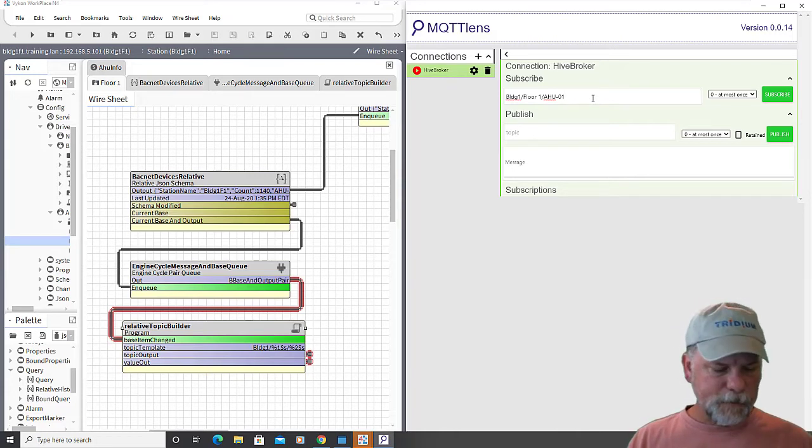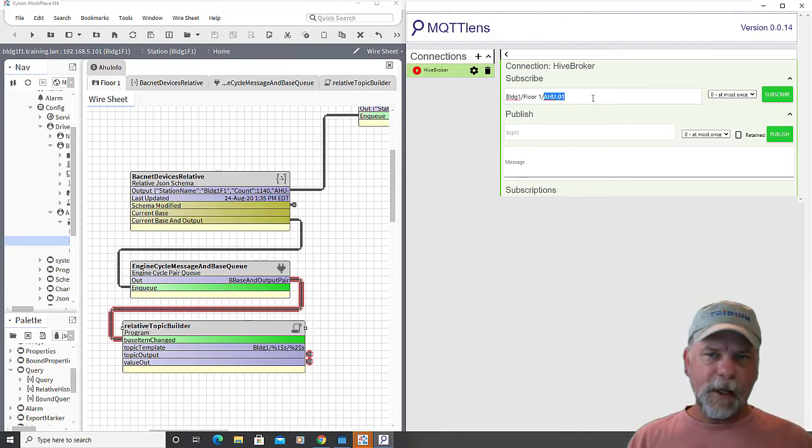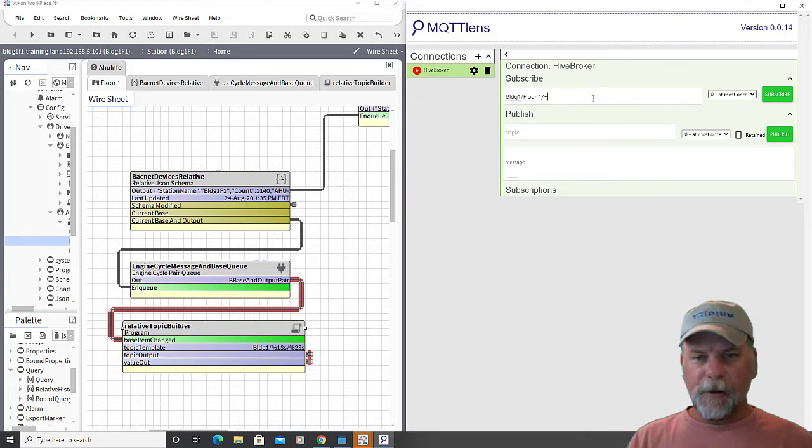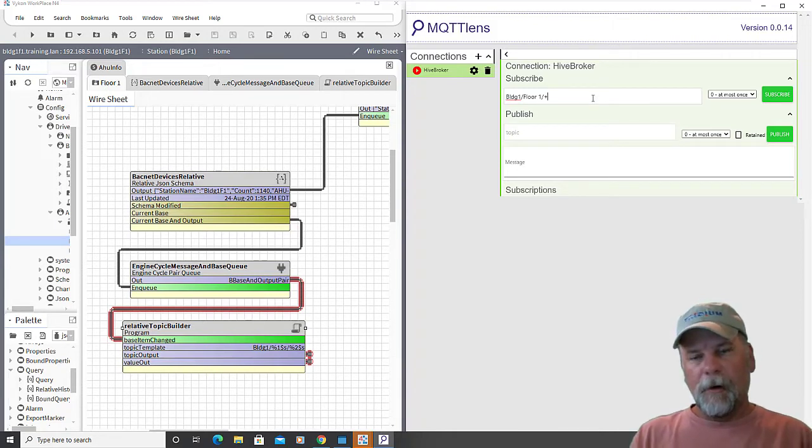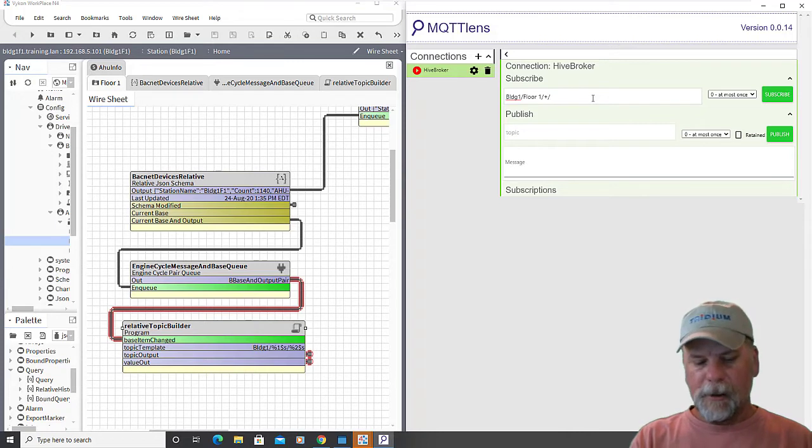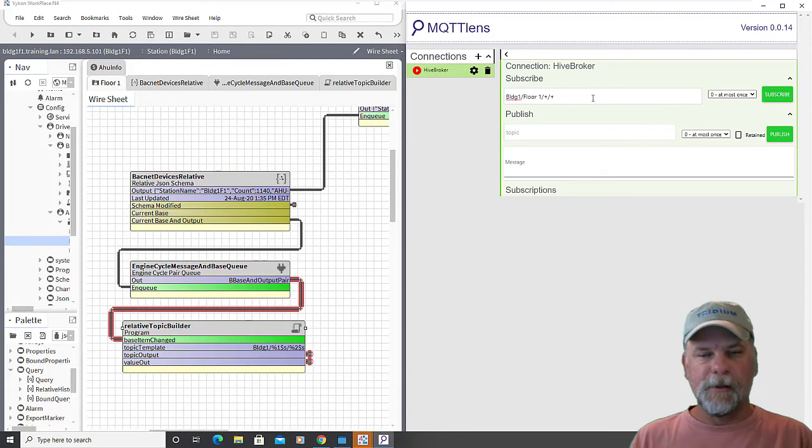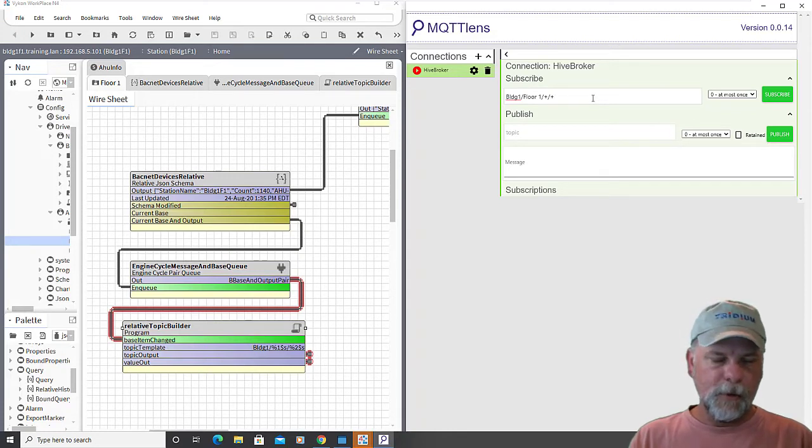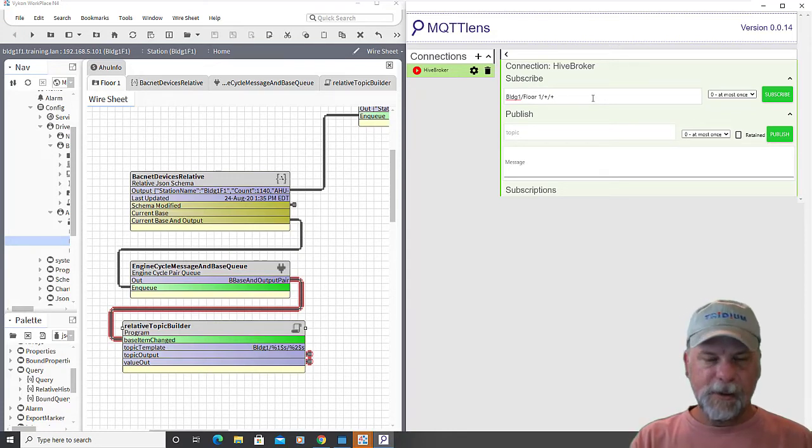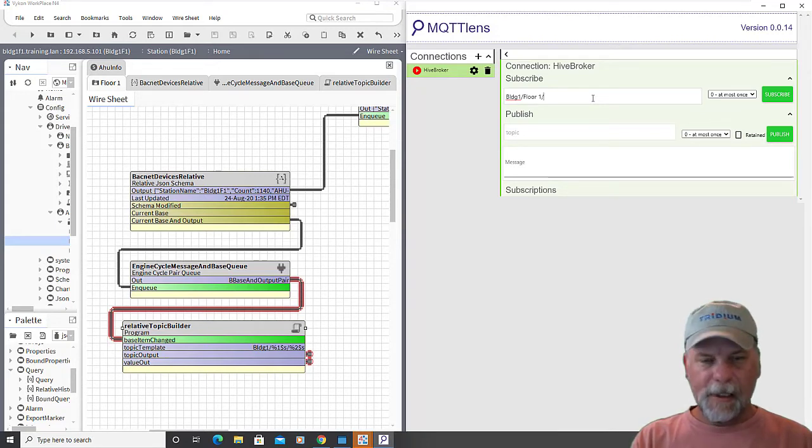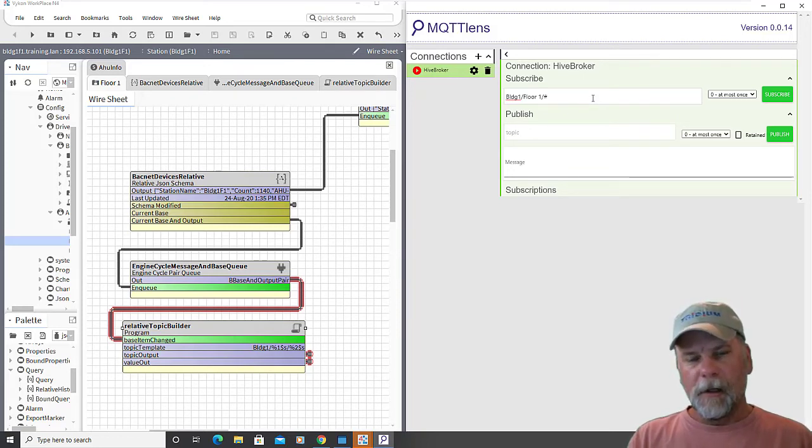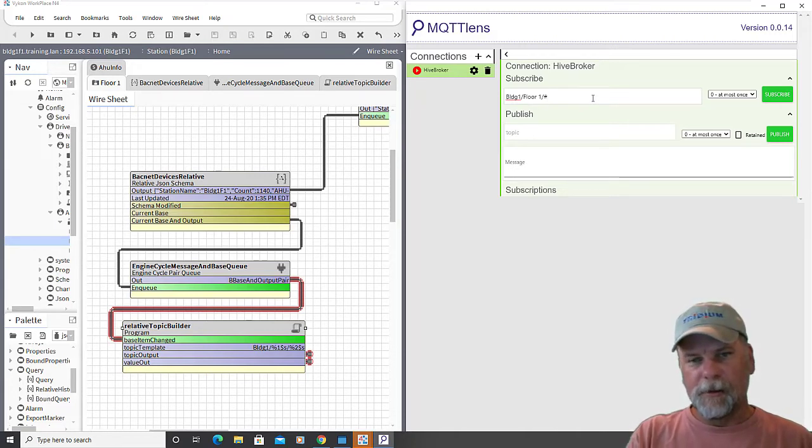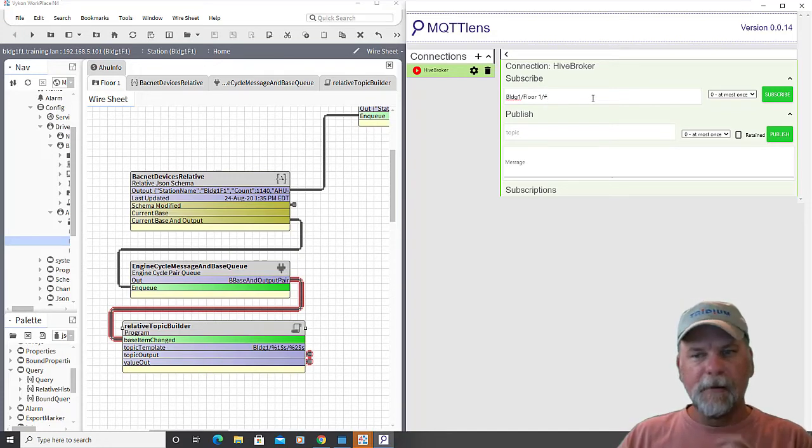Or in this case I could use a wild card. So with MQTT topics subscriptions you can use a plus symbol like that as a wild card to subscribe to. The plus symbol represents a topic level. So I could have slash plus again. So that could be floor one slash air handler one slash points or whatever topic arrangement I had. But each plus symbol is a wild card for a topic level. Or the hash symbol or the pound symbol is a wild card that can go at the end of that topic subscription. It has to be preceded by a leading forward slash but that symbol represents one or more topic levels after that static reference there.